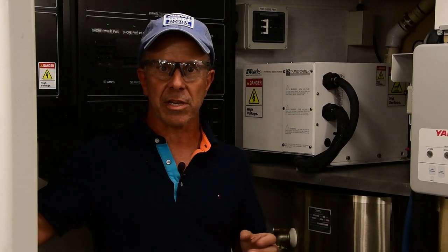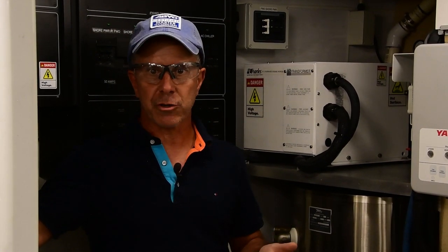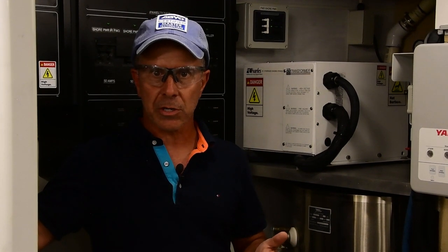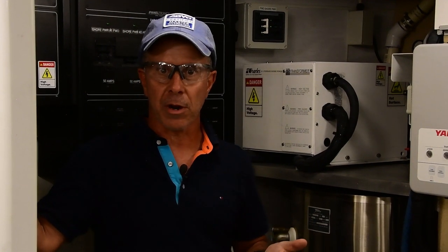On a hot day in the summertime, with all the air conditioning units running on a series of boats on a single dock, it's not unusual to see the voltage as low as 200 or 198 volts. So that means equipment on your boat that's designed to run at a higher voltage isn't getting that voltage. It runs hotter typically, and this primarily affects things like air conditioning compressors, refrigeration units, motors, raw water pumps, things of that sort that would normally run on 240 volts are now getting a lower voltage. They could potentially be damaged.